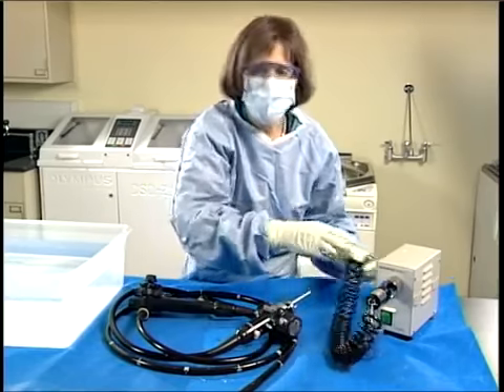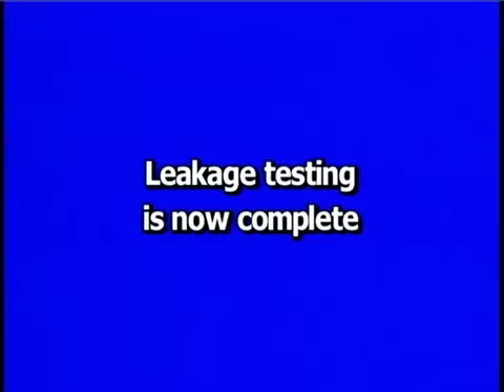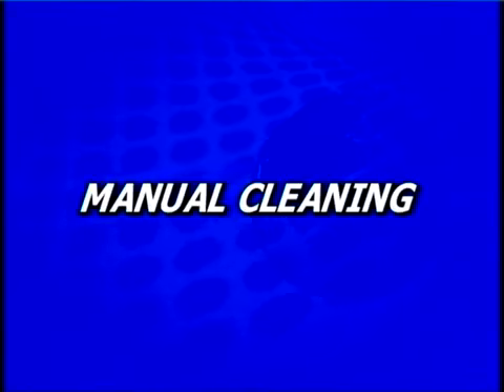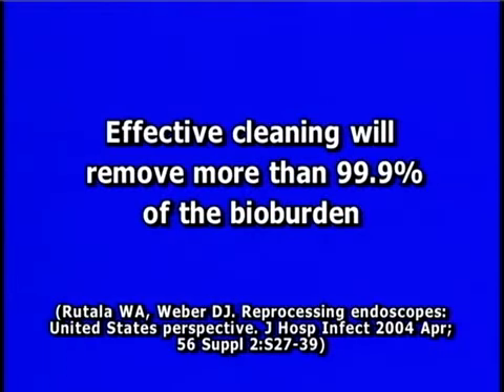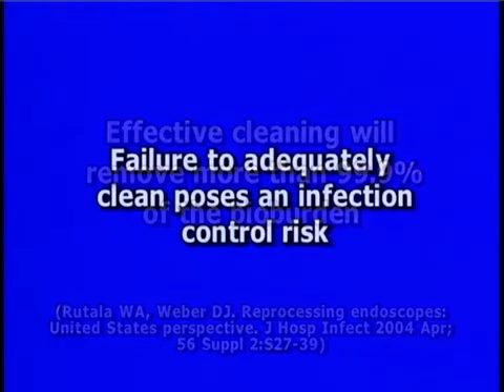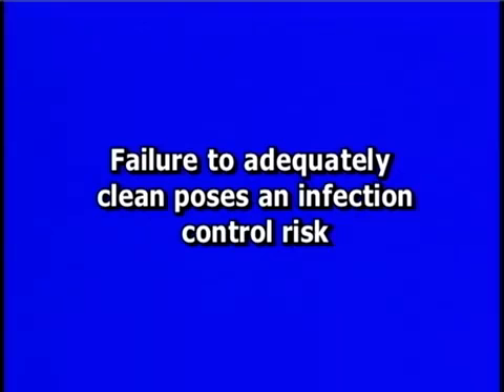Detach the leakage tester from the water-resistant cap. Leakage testing is now complete. The next step is to manually clean the endoscope. Effective cleaning will remove more than 99% of the bioburden from the endoscope. Failure to adequately clean the endoscope will reduce the efficacy of any high-level disinfection or sterilization procedure which follows, and poses an infection control risk.